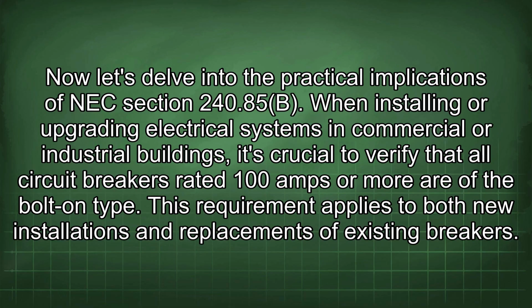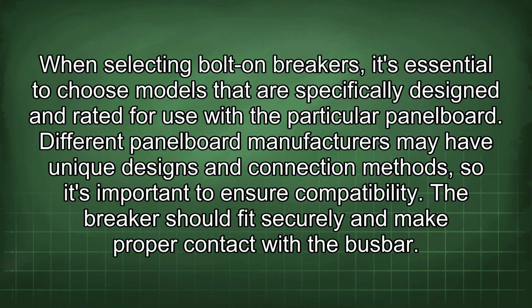Now let's delve into the practical implications of NEC Section 240.85b. When installing or upgrading electrical systems in commercial or industrial buildings, it's crucial to verify that all circuit breakers rated 100 amps or more are of the bolt-on type. This requirement applies to both new installations and replacements of existing breakers. When selecting bolt-on breakers, it's essential to choose models that are specifically designed and rated for use with a particular panel board. Different panel board manufacturers may have unique designs and connection methods, so it's important to ensure compatibility. The breaker should fit securely and make proper contact with the busbar.